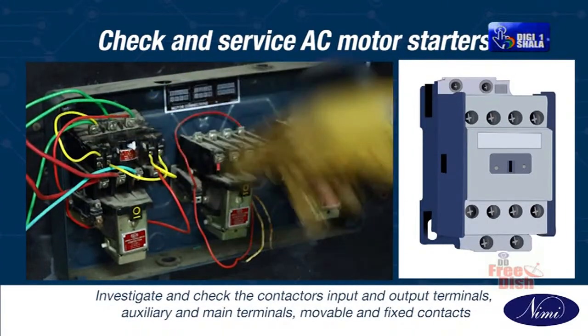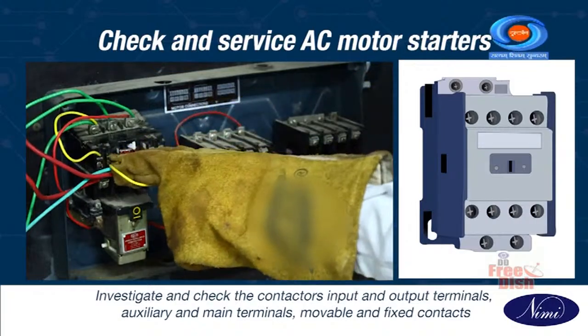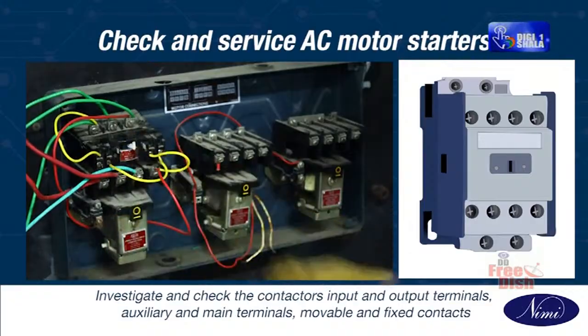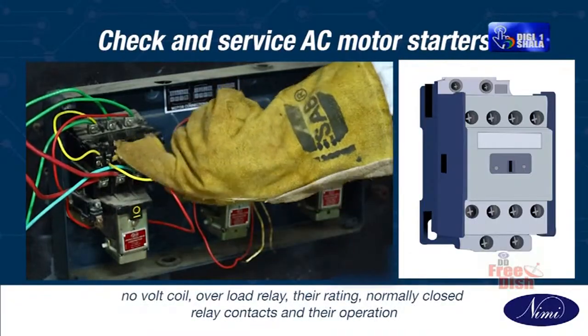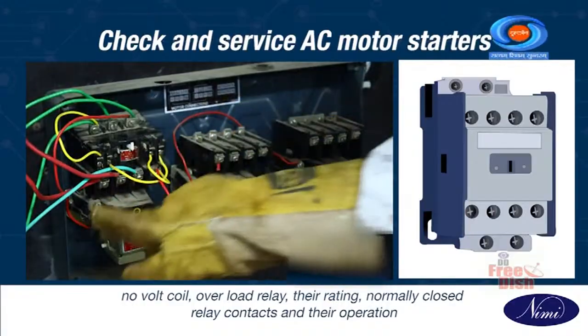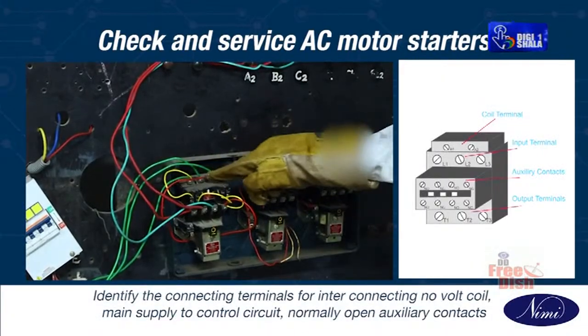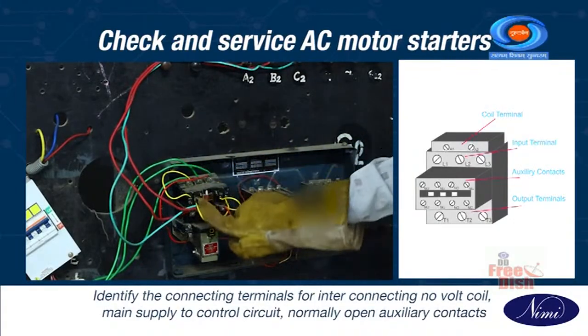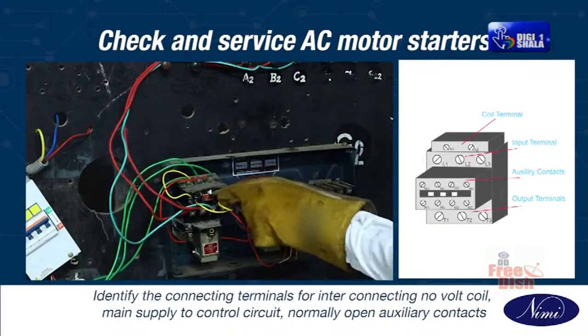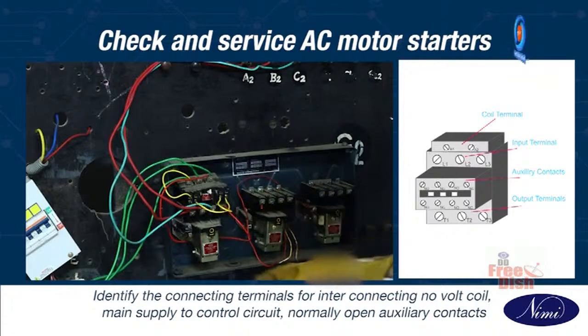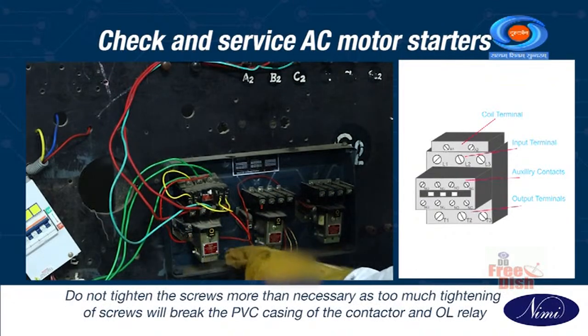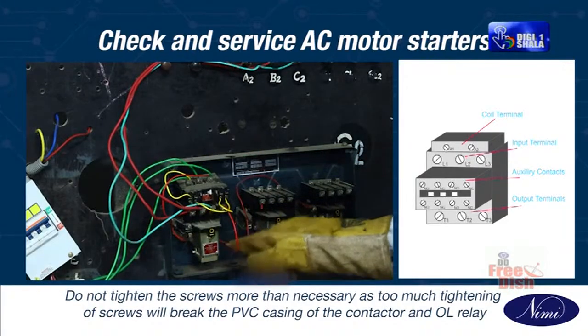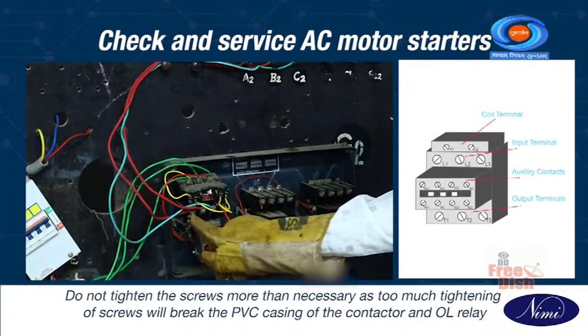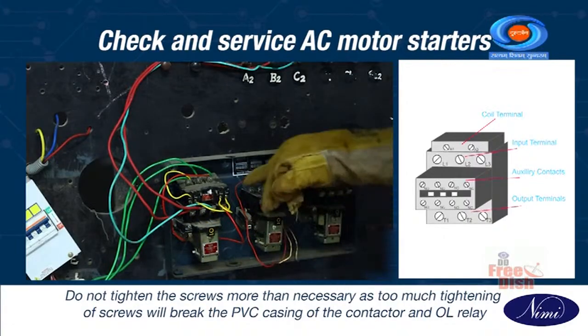Investigate and check the contactor's input and output terminals, auxiliary and main terminals, movable and fixed contacts, no volt coil, overload relay, their rating, normally closed relay contacts and their operation. Identify the connecting terminals for interconnecting no volt coil, main supply to control circuit, normally open auxiliary contacts. Do not tighten the screws more than necessary, as too much tightening of screws will break the PVC casing of the contactor and OL relay.